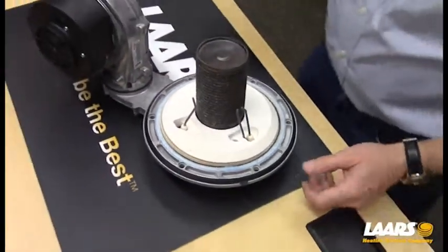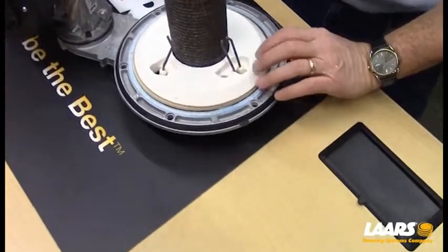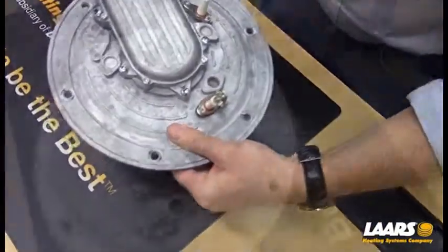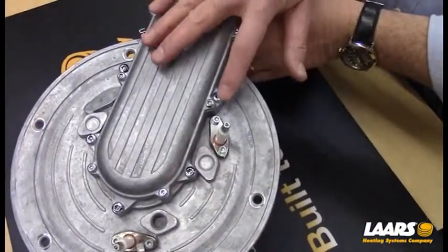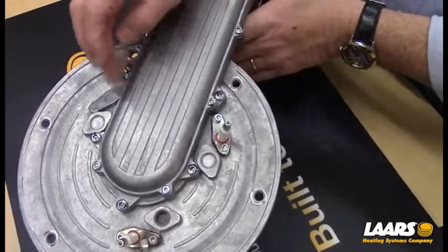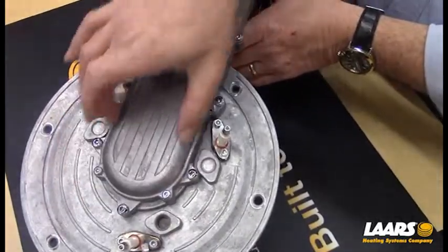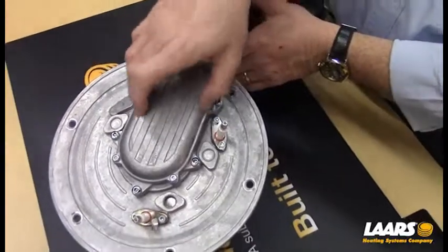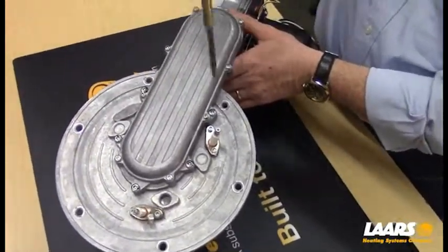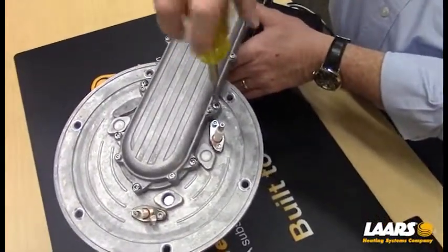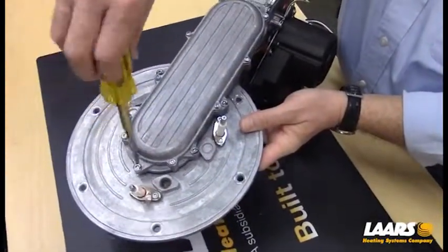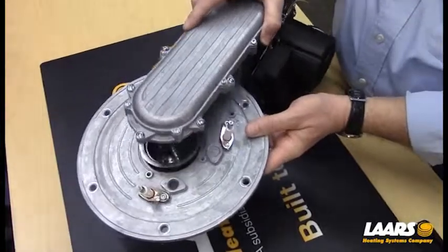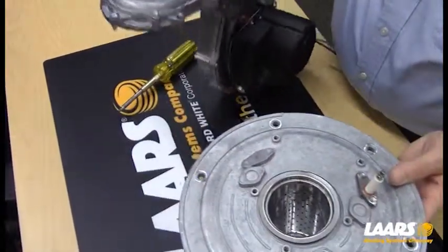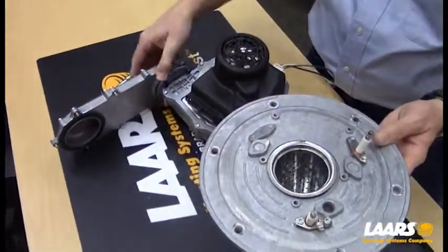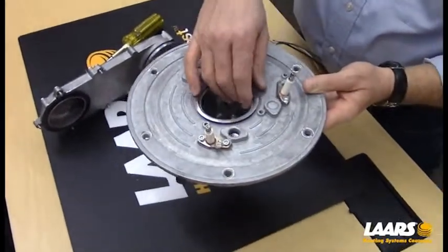So, to remove those, if you had to clean them, I'm going to flip this over. All right, so what we have here, there are 5 T-25 Torx bits. 1, 2, 3, 4, 5. That holds the arm to the burner plate. So I'm simply going to remove these 5 T-25 Torx bits. So I've loosened all the T-25 Torx bits, and I'm going to pull the arm right from the burner plate. Okay, and there's the arm, and here is our burner.